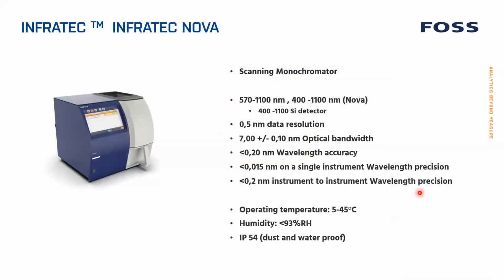The new Infratecs, the TM and the Nova, are scanning monochromators. The TM works from 570 to 1100, while the Nova works from 400 to 1100. And as with the DS2500 and F, this is just a marketing thing. There are different prices on them, so there must be a difference on the instruments as well. One of those things that differ is the wavelength range. Now, all the calibrations we have are from 850 to 1050, so all the calibrations work on both instruments. It's only if you want to develop something yourself that you need to look at the wavelength range.